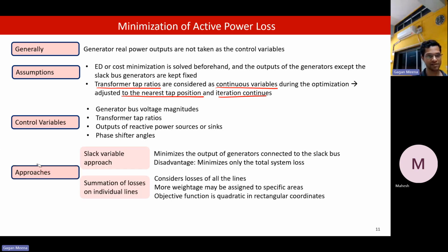These are the two approaches. First one is the slack variable approach. Here we minimize the total system loss. So we minimize the output of the generators connected to the slack bus, because we assume that the losses are supplied by the slack bus. If we minimize the output of the generators connected to the slack bus, then we will minimize the total system loss. So this is the advantage of this approach, that we minimize the aggregate system loss. But if we want to minimize loss in a particular area, that we cannot do here.